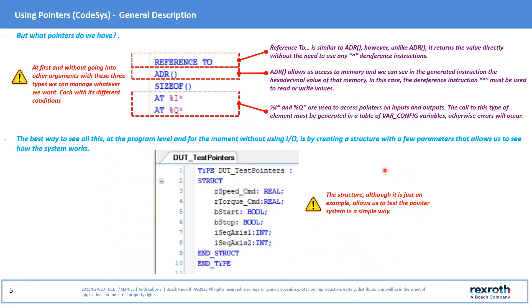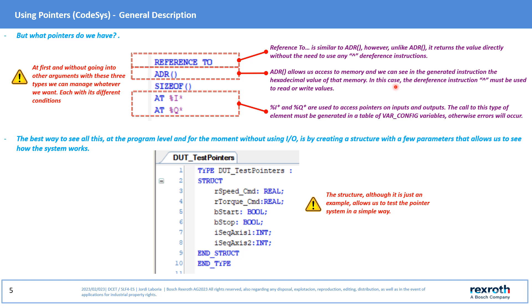At CODESYS we have the following pointers. Reference To pointer. This pointer is similar to ADR pointer, although in this case it is not necessary to dereference the value received. ADR pointer allows access to the memory area in hexadecimal format and it is necessary to use the CARET instruction to dereference the value of the memory area in order to read or write it.